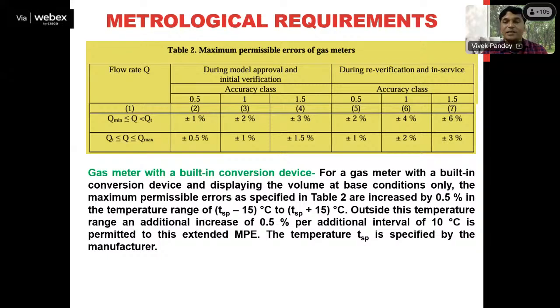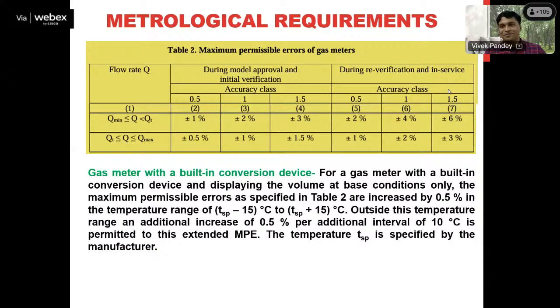So if it is going beyond this range, then it is also mentioned that the tolerance level will change by a further 0.5% for each 10 degrees Celsius increase. For example, specified temperature is 30 degrees Celsius, working temperature is 25 degrees Celsius. So MPE will increase only by 0.5%. But suppose your specified temperature is 30 degrees Celsius. So according to this, the range should be 15 degrees Celsius to 45 degrees Celsius. But suppose the gas temperature or the working temperature is 10 degrees Celsius. So it is beyond this range. If it is within a 10 degrees Celsius extra gap, then 0.5% MPE will be further adjusted or considered.